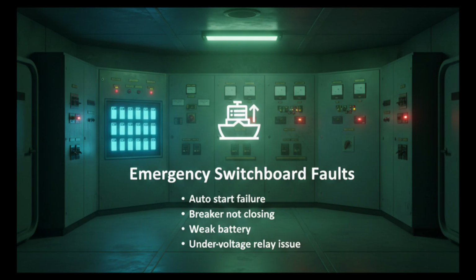Emergency switchboard faults. Emergency switchboard must always be ready. If main power fails, emergency generator should start automatically within seconds. Common problems include emergency generator not auto-starting, breaker not closing, battery weak, and under voltage relay malfunction. Regular testing is extremely important. Check battery condition weekly. Test auto-start function. Verify voltage output. If emergency system fails during blackout, ship safety is compromised. Treat emergency systems as critical life support equipment. Never neglect their maintenance.